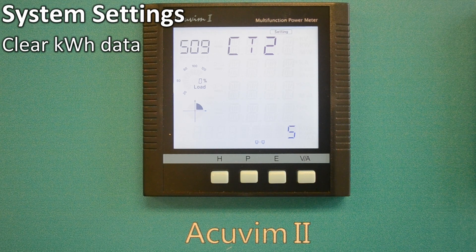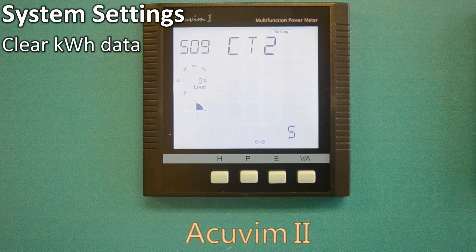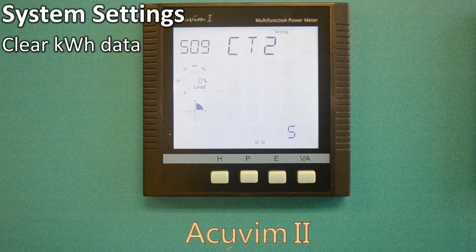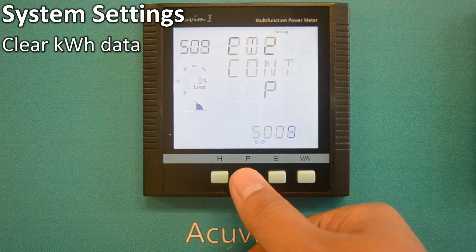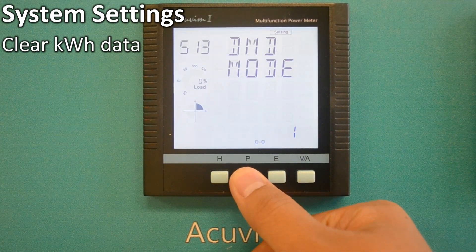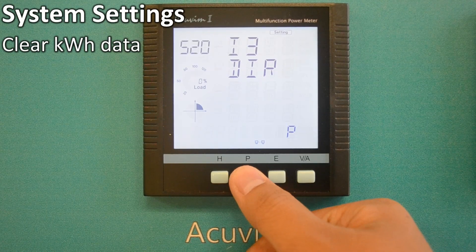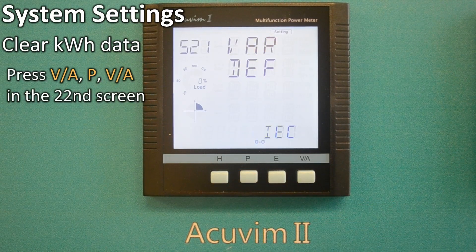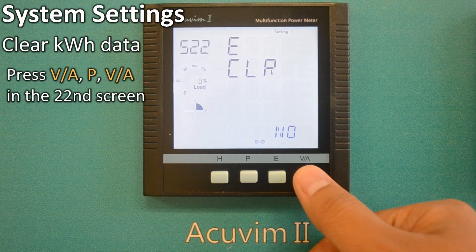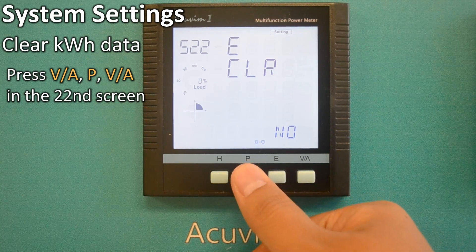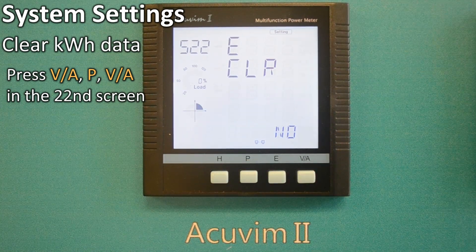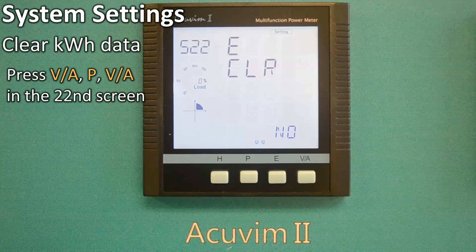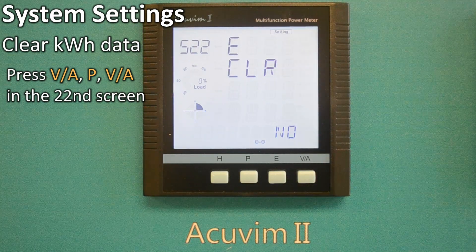Finally, we will clear the kilowatt hour data. If you want to clear the kilowatt hour reading, press P repeatedly until you see a screen named ECLRNO. You then change the setting to Yes by pressing VA, then P, and then confirm by pressing VA again. The kilowatt hour reading will now be cleared.